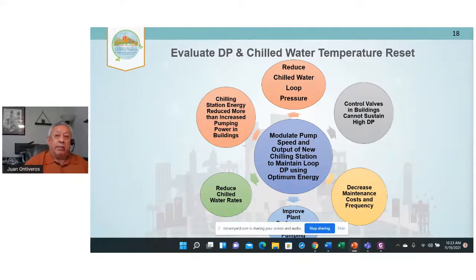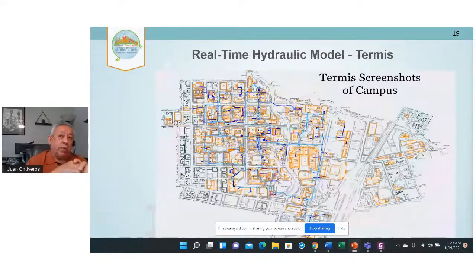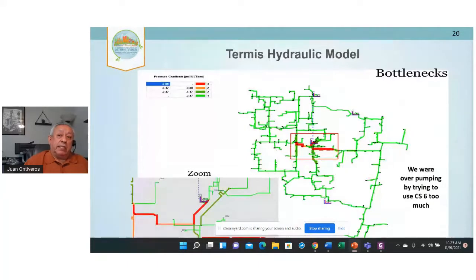And the way we evaluated it is I have a real-time hydraulic model of the campus. What you're seeing here, the light blue lines, are basically our tunnel system. It allows me to see all of my conditions, looking at pressures and flows. It helped us identify that this is where the new chilling station was built. Right here is a snapshot of it. The red lines are saying I have really high flow, too high a flow. So it's restricted flow. I have a bottleneck in the system. So we were over pumping by trying to use chilling station 6 too much.